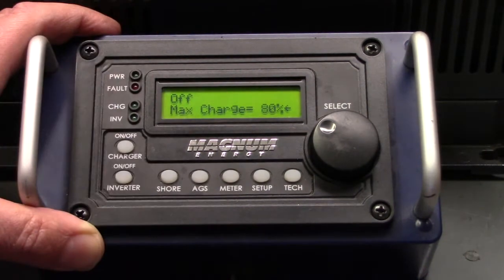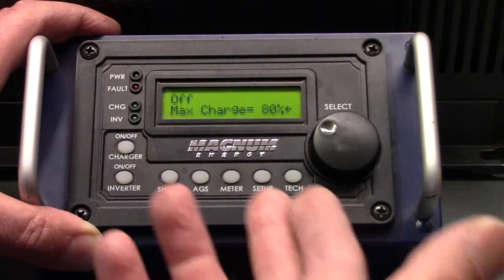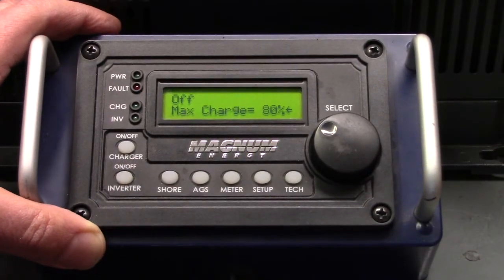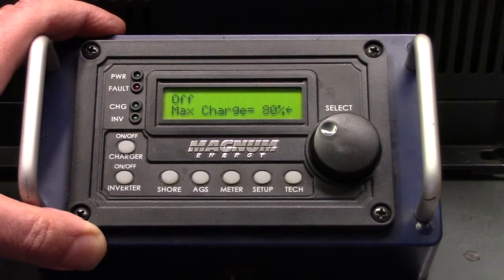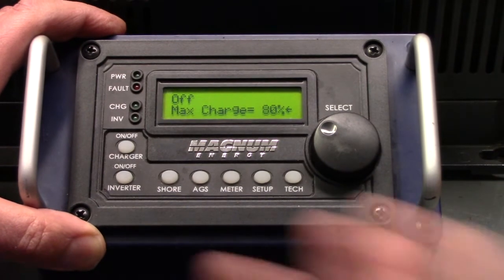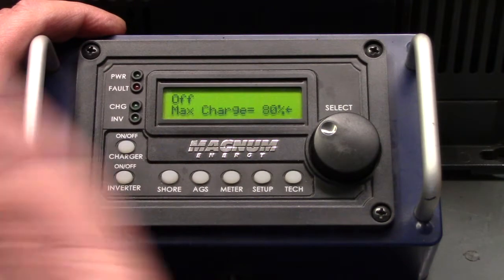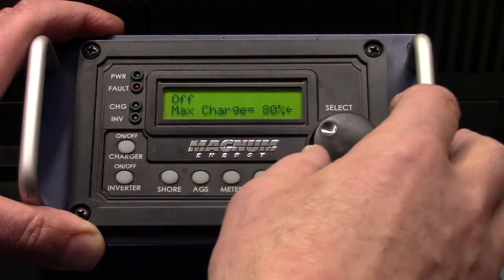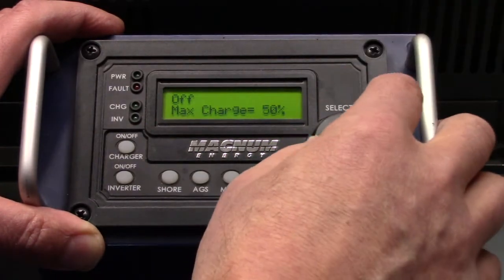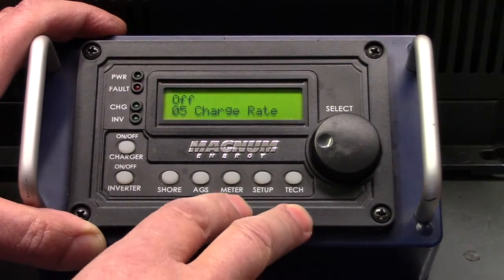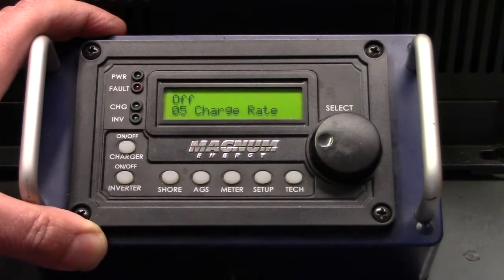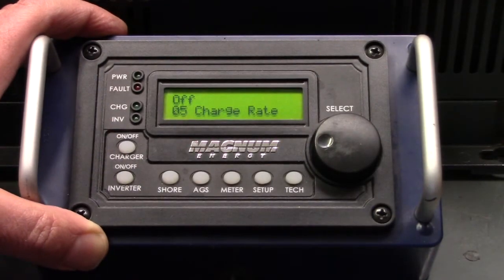But just so you know, as we saw with the test we did with the shore power, the shore power can use up a lot of your shore power current charging your batteries. If you're the type of person who pulls your RV into a spot in the morning, plugs it in, and it's plugged in all day long, there's really no reason to ram 100 amps into your batteries and try to get them charged up as fast as possible. It's hard on the batteries, and it uses up all your shore power. So you don't really need to do that — you could turn this down to say 50 or 60%, and that would lower the amount of current the battery charger draws from shore power. It will take longer to charge the batteries, but if you're going to be parked there all day, who cares? You've got power from the shore power outlet, so you don't really need the battery power anymore while it's charging.